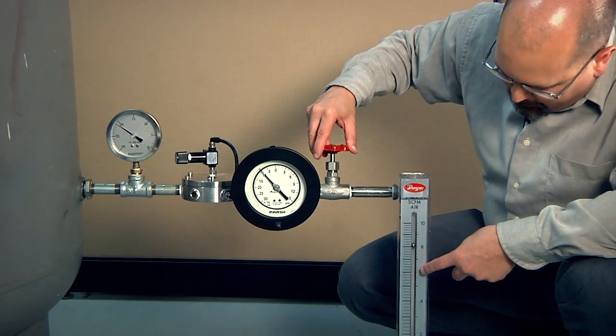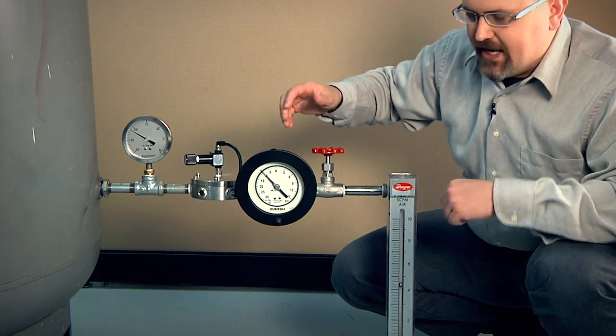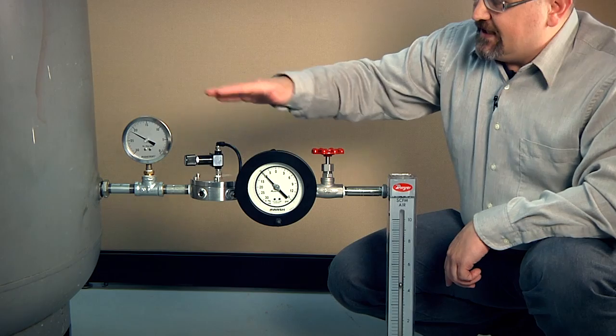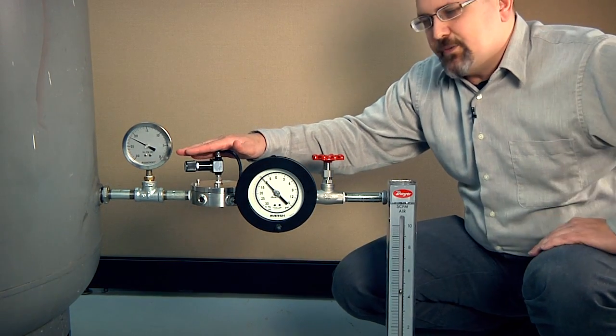The system flow can vary. Different things can happen in your system to make that happen. But the vacuum pressure is dictated and held by the vacuum regulator, the Equilibar vacuum regulator.